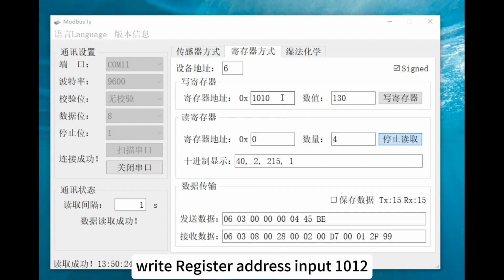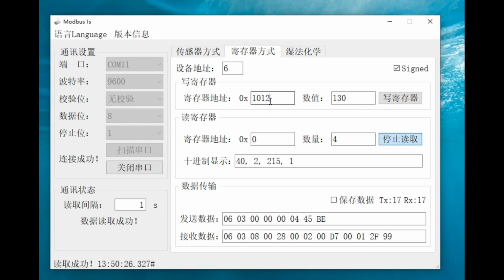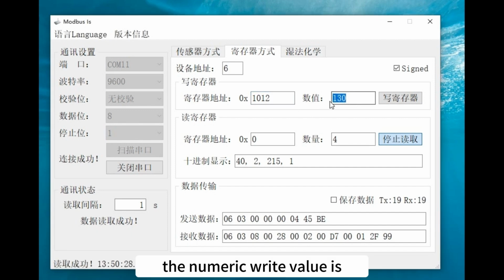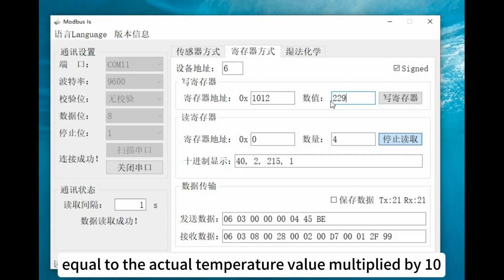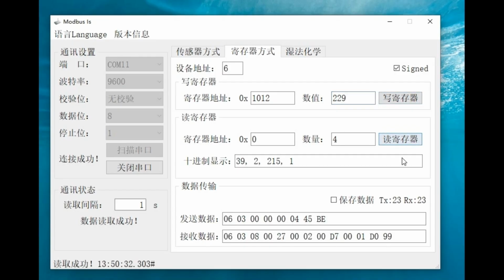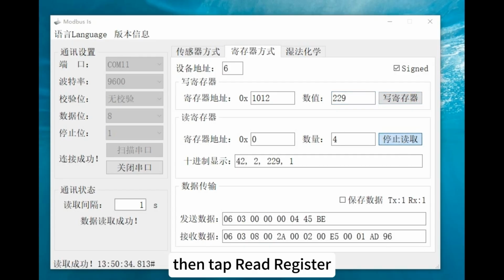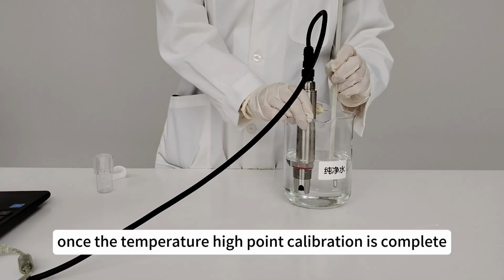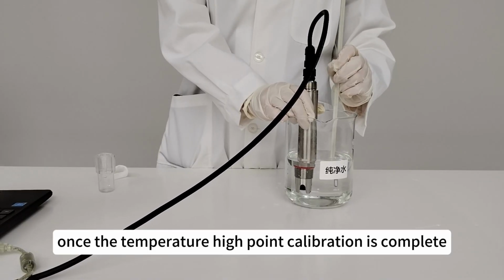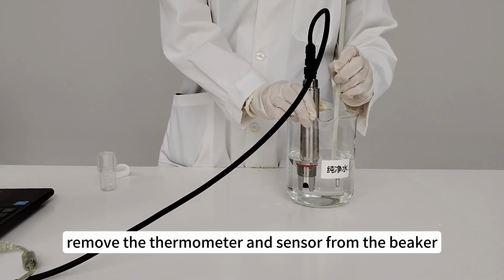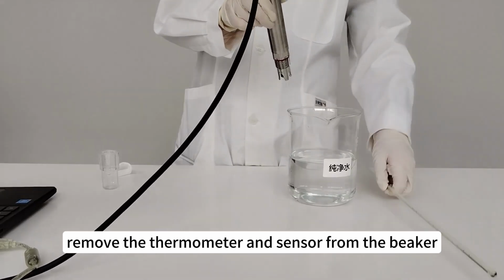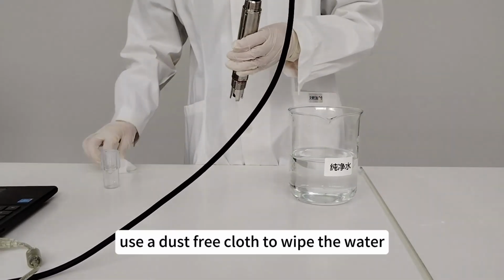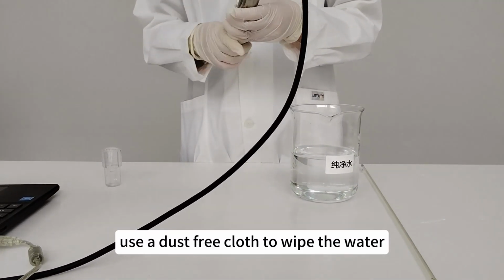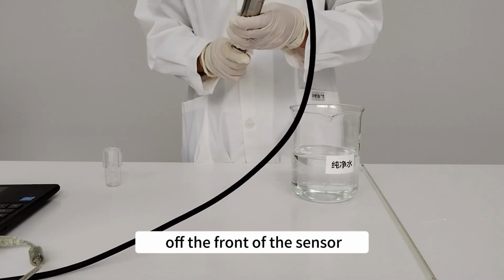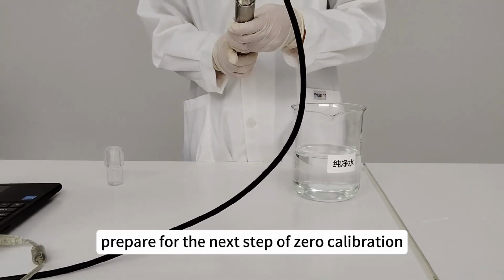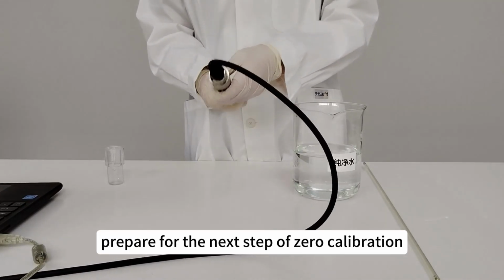Enter 1012 for Write Register Address. The numeric write value is equal to the actual temperature value multiplied by 10. Tap Write Register, then tap Read Register. Once the temperature high point calibration is complete, remove the thermometer and sensor from the beaker. Use a dust-free cloth to wipe the water off the front of the sensor. Prepare for the next step of zero calibration.